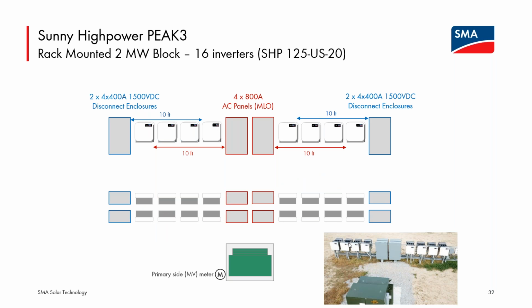And setting up plants like this is very straightforward to come to what is not a very large 2 megawatt block. The 125 kilowatt unit, again, a 480 volt transformer, pretty straightforward. 1, 2, 3, 4. You have 8 by 125, so you have 1 megawatt here and 1 megawatt here. AC collection panels for the groups of inverters. Lots of areas you'll have DC disconnect needs, and so some folks have asked about a combiner box at the array and a DC disconnect at the inverter. We're investigating DC disconnect enclosures that would work with a plant layout like this, where each group of inverters would also have DC disconnection options very, very close.